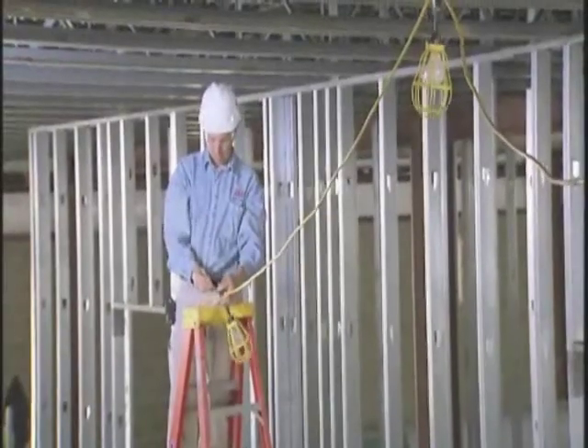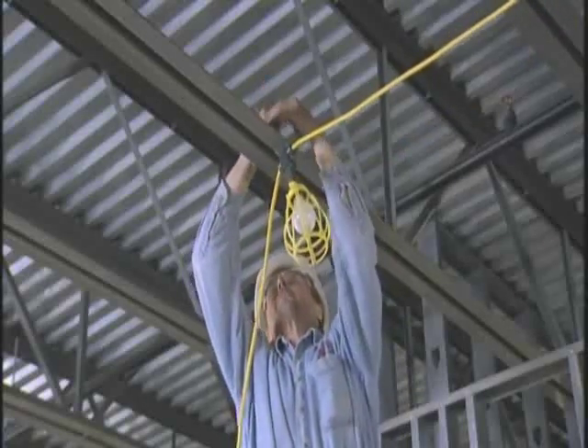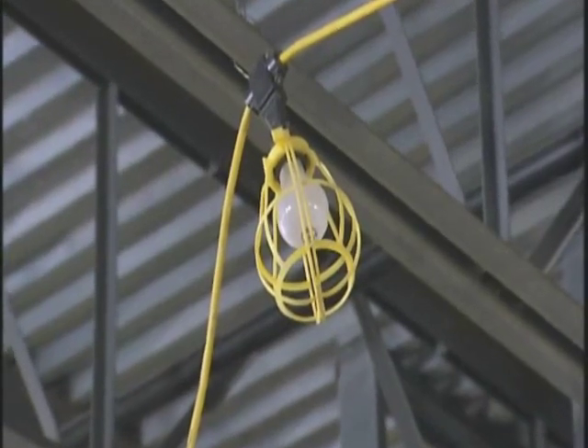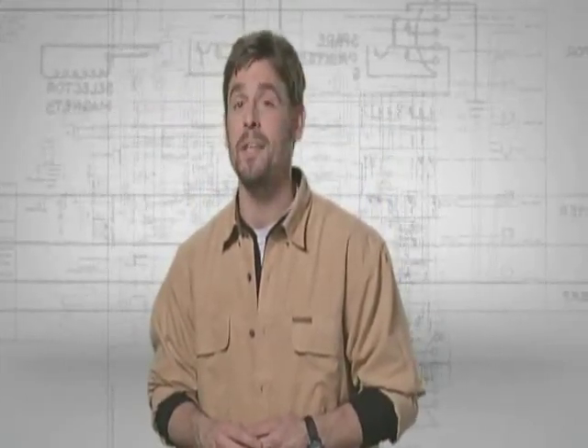While NM cable is used for temporary wiring, it must be supported and protected from damage. Regarding temporary lighting, hanging temporary lighting by the wiring or fixtures is a bad idea unless the fixture was designed for this purpose — and not many are. You could be creating a shock hazard. Don't use unguarded temporary light bulbs; make sure the bulb has a protective cage surrounding it. When you've gotten away with sloppy work habits for years, some workers become complacent.